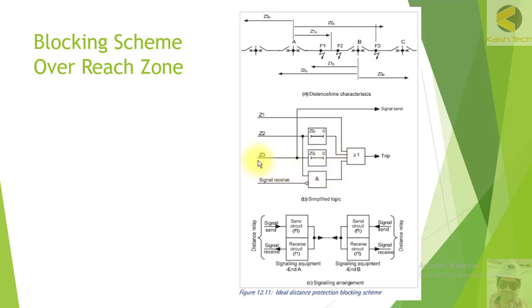Looking at the logic diagram: if the relay picks up in zone 3 — which is used as the reverse zone in this case, though it could be zone 4 or zone 5 depending on the relay — it sends a blocking signal to the remote end. In modern numerical relays, we have the feature to select any zone in the forward or reverse direction. If the relay picks up in the reverse zone, it immediately sends a blocking signal.